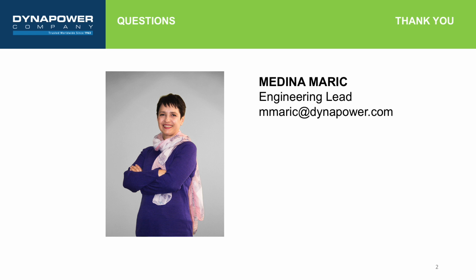Thyristor rectifiers, depending on the overall system topology, can go to a very complex design. The more pulses the topology has, the more complicated the transformer is. Some of those transformers will contain IPTs. Some will have higher kVA input. That all depends on the rectification and the circuit that is selected. So the losses of those transformers can go up. And also, if the DC voltage needs to be regulated, some of the transformers can include multiple tap changers. So the complexity of the transformer goes significantly higher.